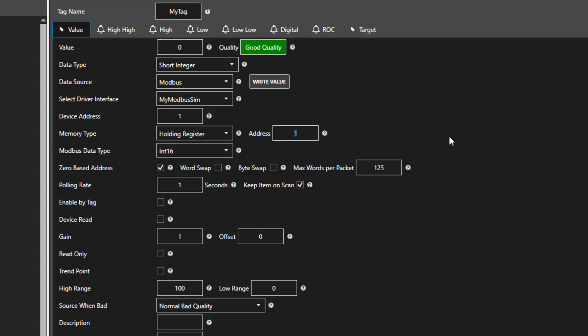Here we select the address. It depends upon the memory type that you have selected as to what is added to that address. The default is an address of 40,001. The holding register base is 40,000. Then an address of 1 makes it 40,001 in the Modbus device. You can also use extended addressing with the Modbus communication driver.